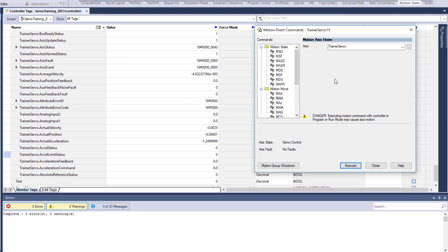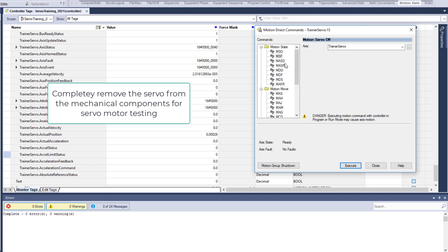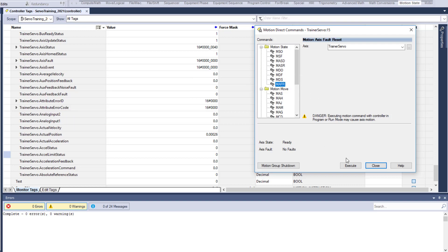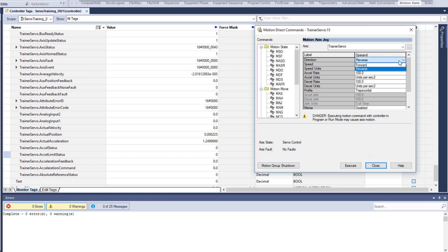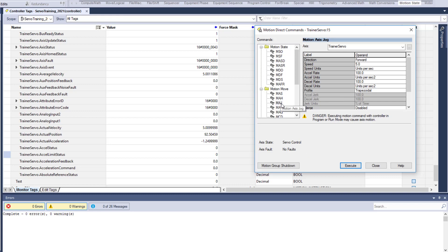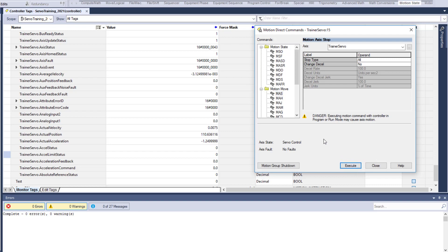If the servo moves and you don't have any kind of limitations — say you uncoupled the servo from the mechanical limitations — you come over here and issue an off, issue a reset, issue a motion axis on, and then control it. If it runs uncoupled, then there's nothing wrong with the motor. Then you need to troubleshoot the mechanical limitations of the system, or look at other issues like dirty or clean power problems. If it does run, 90% of the time it's not the motor.